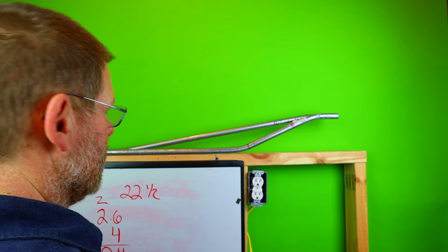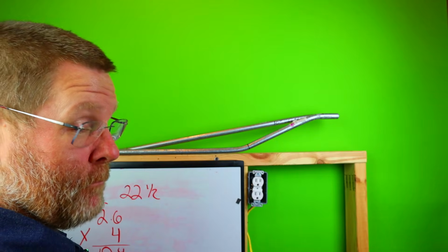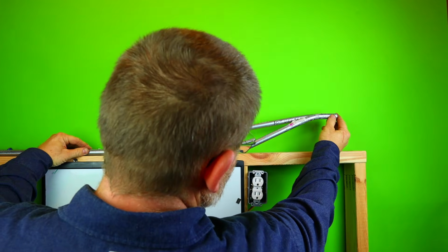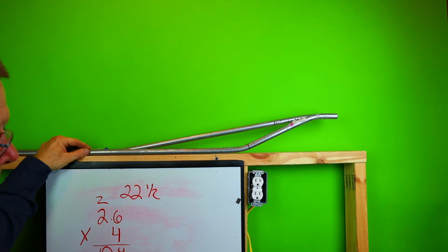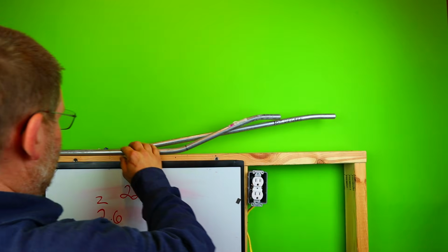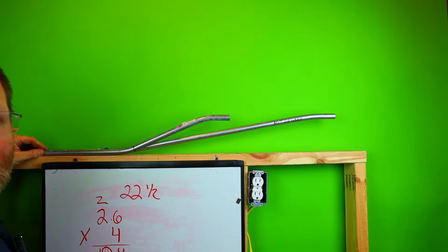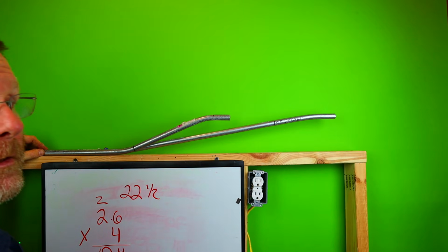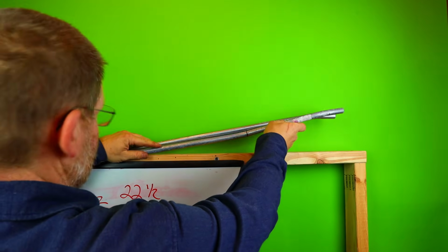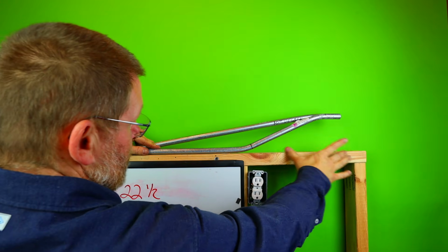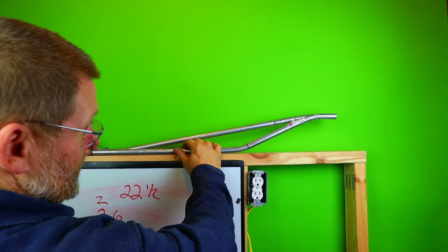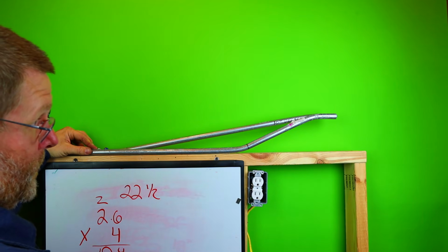So like I said, the 0.4, most electricians just, but do you see what I'm talking about? The difference here between 10 degrees and 22? Do you see the real estate? I mean, if you match the bends, at least the first bend, look how much difference it is. That's pretty incredible. I mean, do you see the difference? I'm talking about how you've got to decide how much room do you have. Because here on the 10 degree, you got all this room. And then here on this 22 degree, you only have that much.